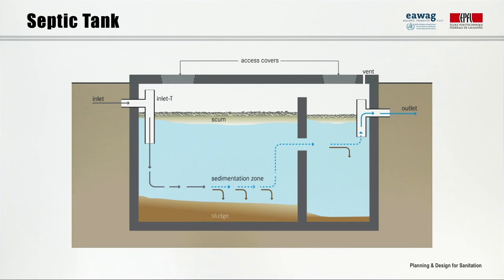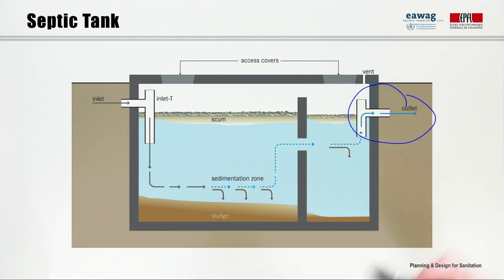The septic tank is among the most widespread on-site sanitation technologies. There are two important things to know about the septic tank. First, it is a watertight tank, typically made of reinforced concrete, polyethylene or fiberglass. And second, it has an outlet through which the clarified effluent leaves the tank. In practice, people are not always aware of those two aspects — they may even call an open bottom pit a septic tank, which is actually wrong.